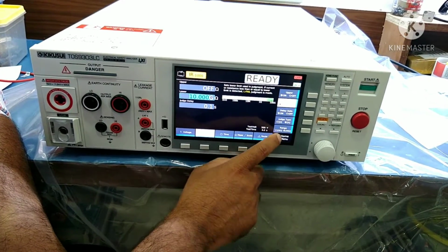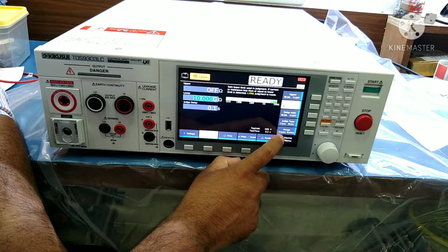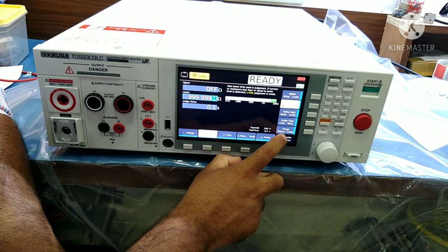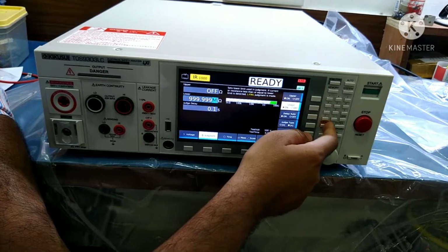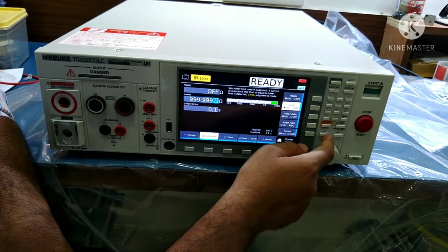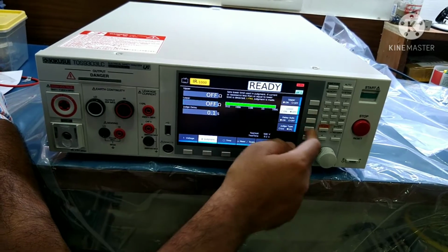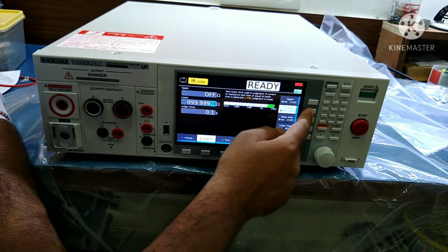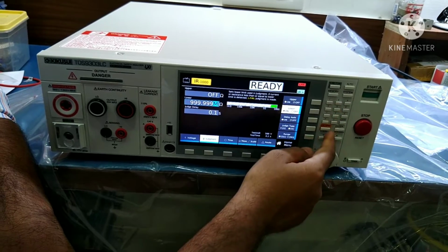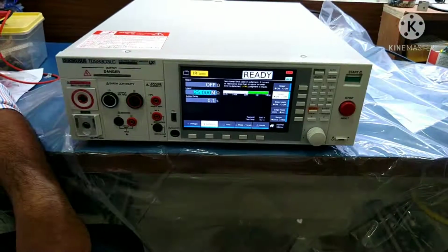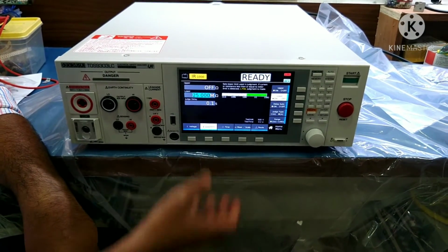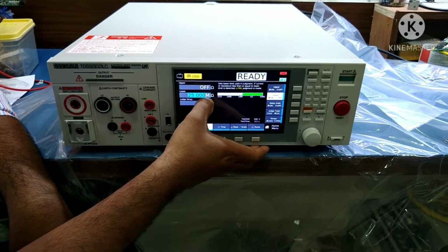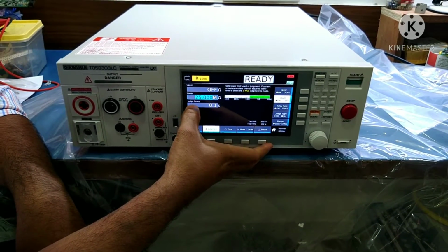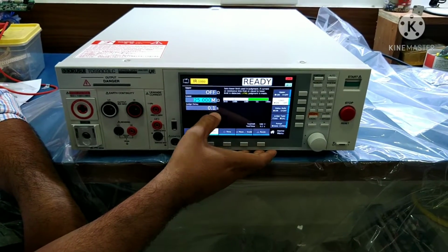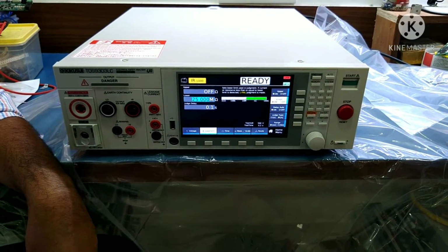Here you can also change between mega ohm and giga ohm. Right now it is set to giga ohm, so I am going to set it to mega ohm. So we are going to set the 25 mega ohm lower value, and now the judgment delay is 0.1 seconds. If you want to set more time, you can set it as per your requirement.